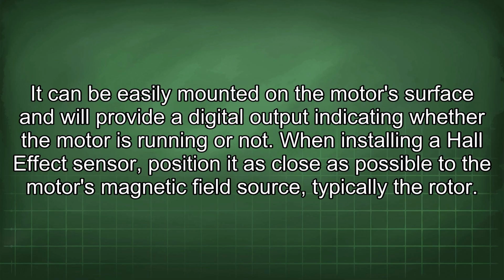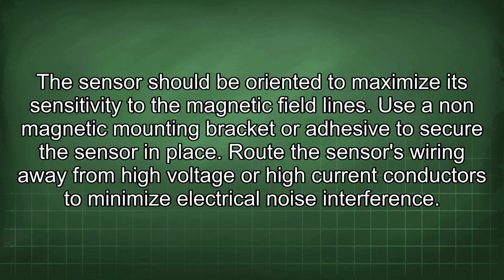When installing a Hall effect sensor, position it as close as possible to the motor's magnetic field source, typically the rotor. The sensor should be oriented to maximize its sensitivity to the magnetic field lines. Use a non-magnetic mounting bracket or adhesive to secure the sensor in place. Route the sensor's wiring away from high voltage or high current conductors to minimize electrical noise interference.